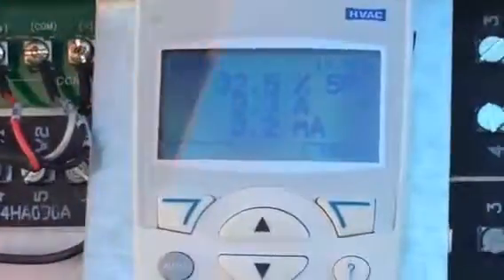Another item you'll see on your ABB keypad, next to where it says auto, and always make sure that says auto, is the spinning arrowhead, clockwise or counterclockwise. When it's spinning, it means it's moving towards that set point. I'm asking for 33%, it's 32.5. That's why it's moving, showing me that it's not there yet, it's on the way. Usually you always see them moving a little bit. So that's the speed. I can always expand out to have it spell it out to me.